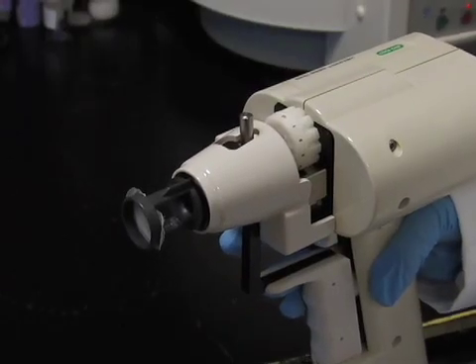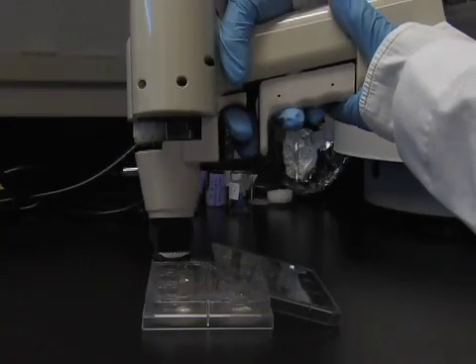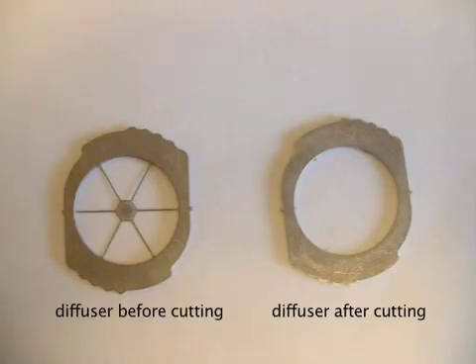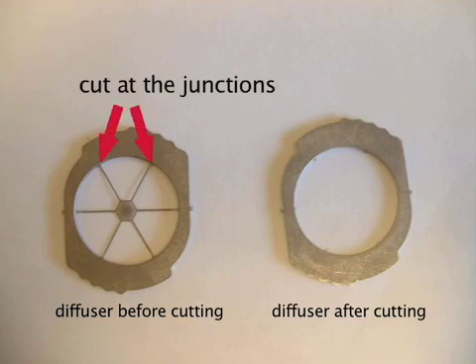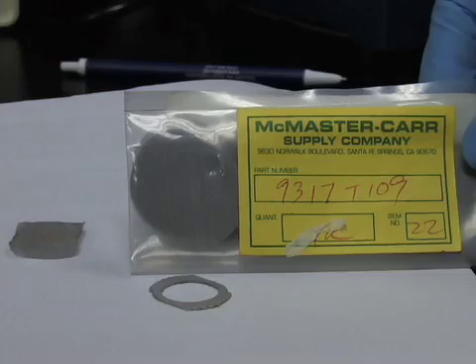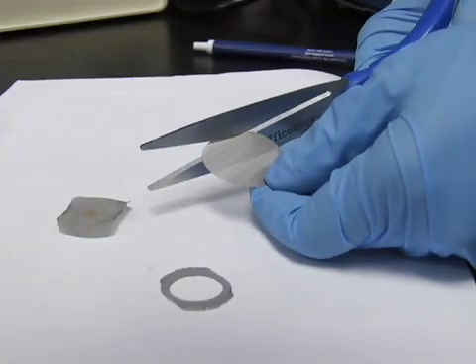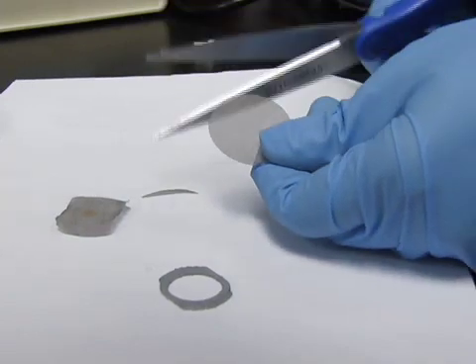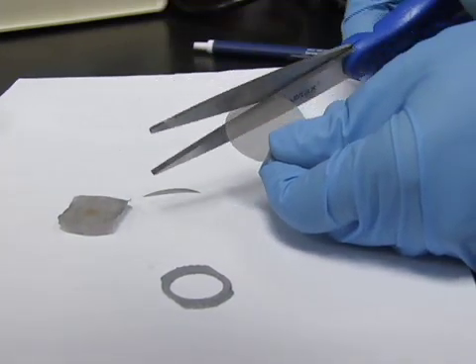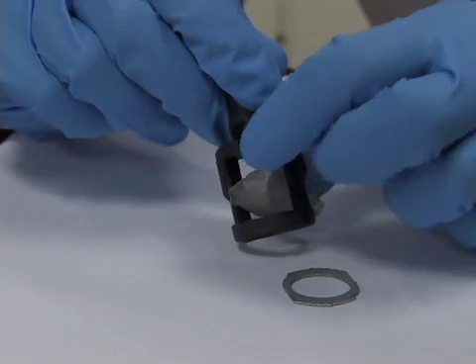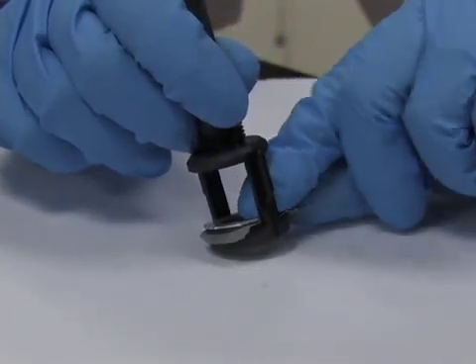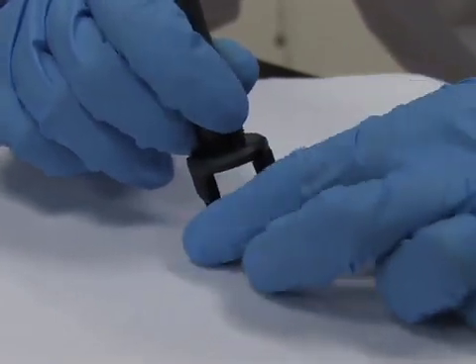Sometimes shooting can lead to unhealthy slices. Often, unhealthy slices result from the pressure blast. The Helios gene gun system comes with the diffuser with a metal cross at its center. We cut out the inner metal cross and instead use a metal screen in place of this cross. We simply cut the screen a little larger than the end of the barrel liner and pinch it between the end of the barrel liner and the cut diffuser. We have found that this improves the health of slices.